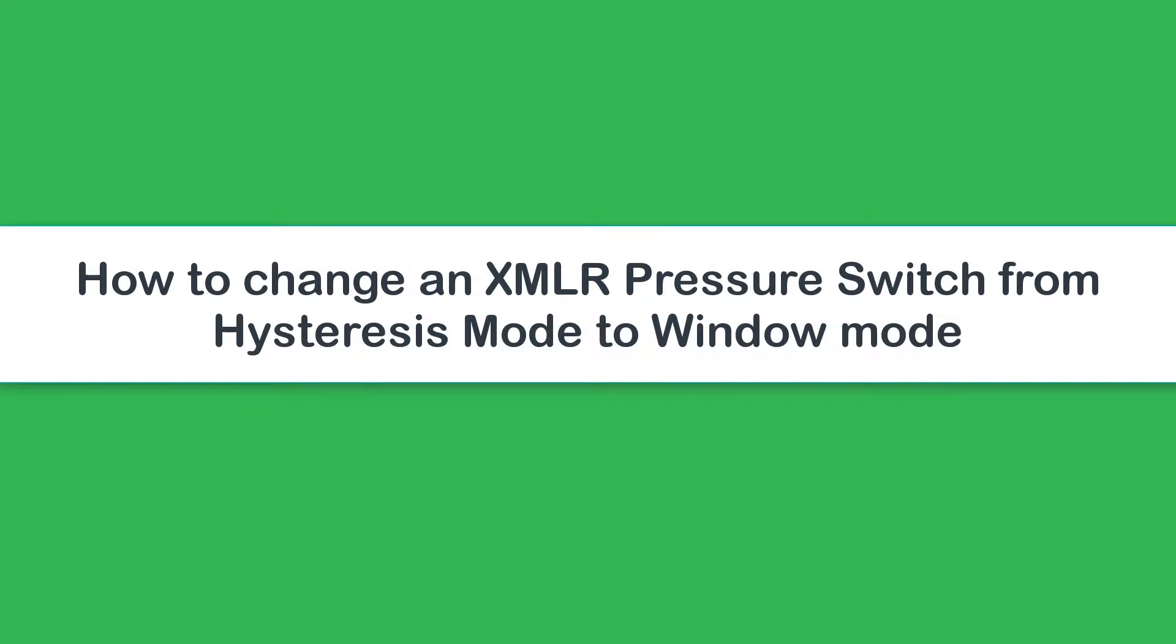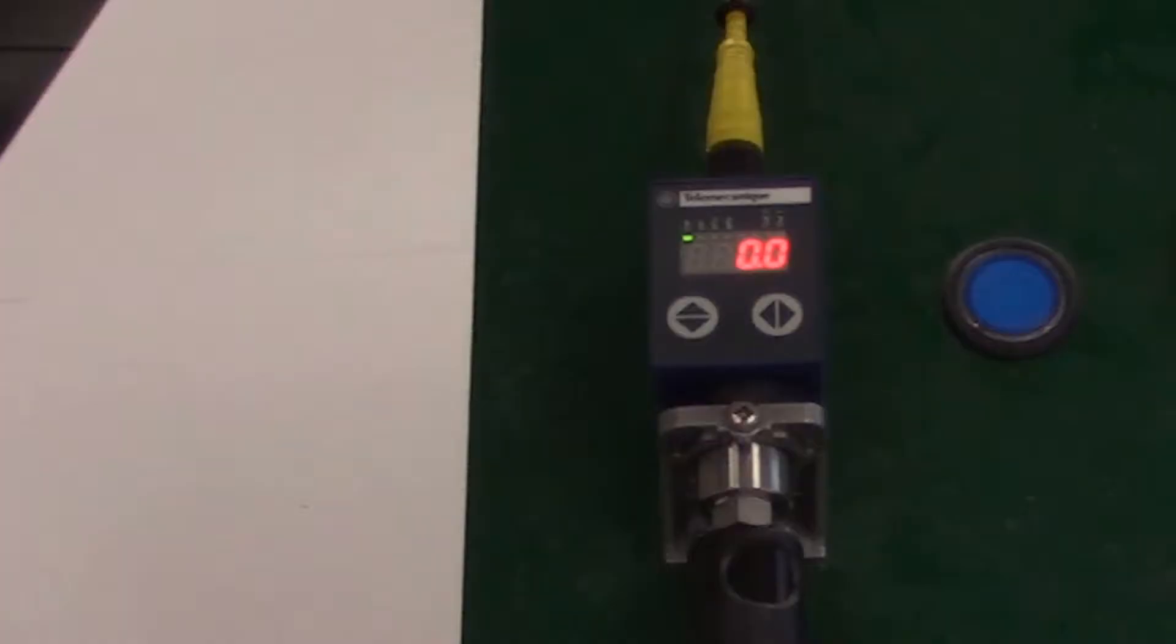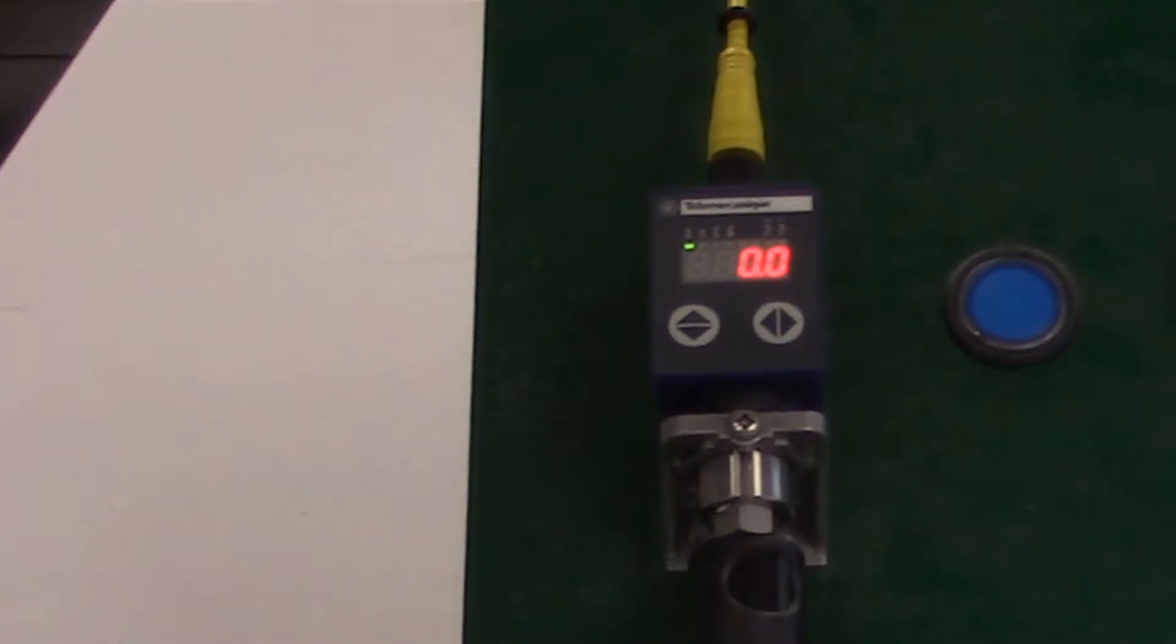How to change an XMLR pressure switch from Hysteresis mode into Window mode. Hysteresis mode normally open is the default mode for an XMLR pressure switch. Hysteresis mode is useful for applications such as pumping or filling and emptying of vessels.